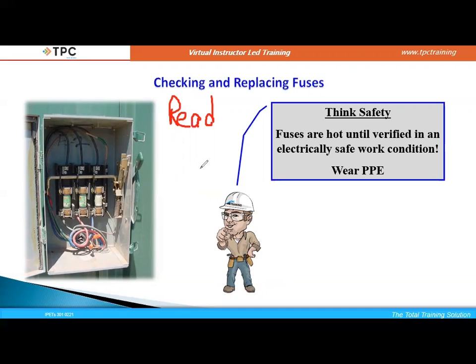And remember, we can't just randomly change these fuses to a different size or a different class, because it will change our clearing time, and that could impact safety. Now, I also did say that we can check these while they are energized. OSHA does allow us to do this. They're calling it troubleshooting, but we do have to wear the proper personal protective equipment. So hopefully you have arc flash warning labels in your facility, and you can make that determination based on the incident energy and voltage that is present at this disconnect.